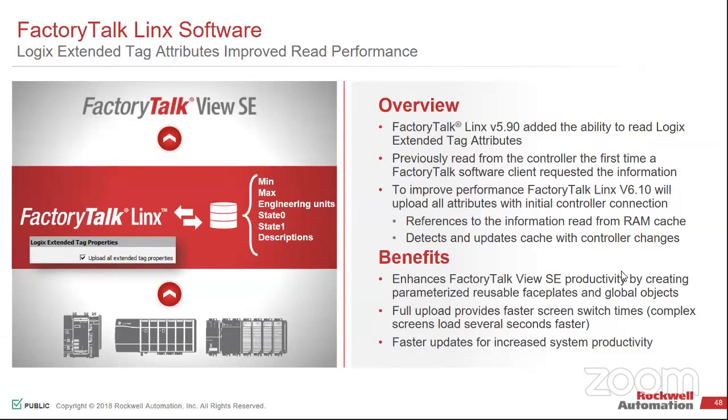So in most cases, once you spin up your controller, the HMI at first scan grabs all that information, sucks it into the HMI, shows it, and now you can also interface with it. In FactoryTalk View SE, and the FactoryTalk side from the panel view side, you can display that information. So now instead of having to manually type all that stuff in, it's part of the code and it is saved in the controller.